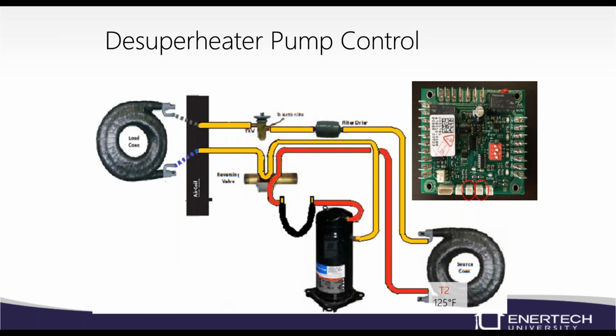Now we've got 125-degree discharge gas, 115-degree water. It says my discharge gas is greater than my water temperature. So now I would go ahead and turn on the pump and run our de-superheater circuit until either T2 is less than T3 or T3 has reached the 130-degree limit. So now we just don't run the de-superheater pump all willy-nilly. We actually compare numbers and say, okay, yeah, we'll go ahead and run the pump, or no, we don't. It just saves us a little bit of pumping power and wasted energy. A unit that does not have a de-superheater will not come with that T3 sensor. We're just not going to ship it. It will have a T2 because we still do want to look at discharge gas temperature.